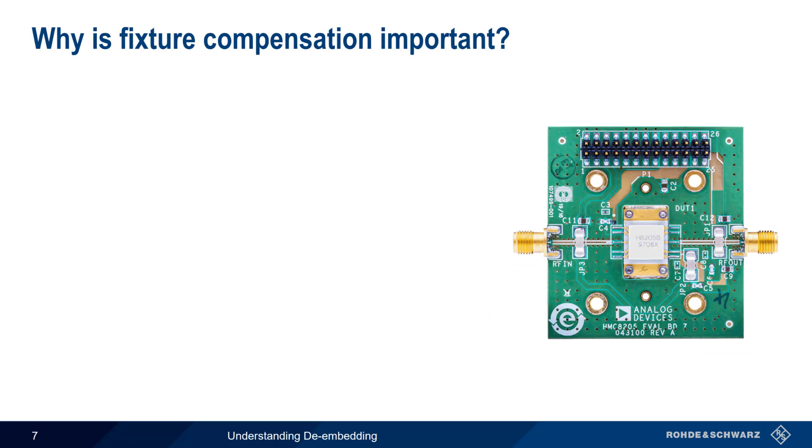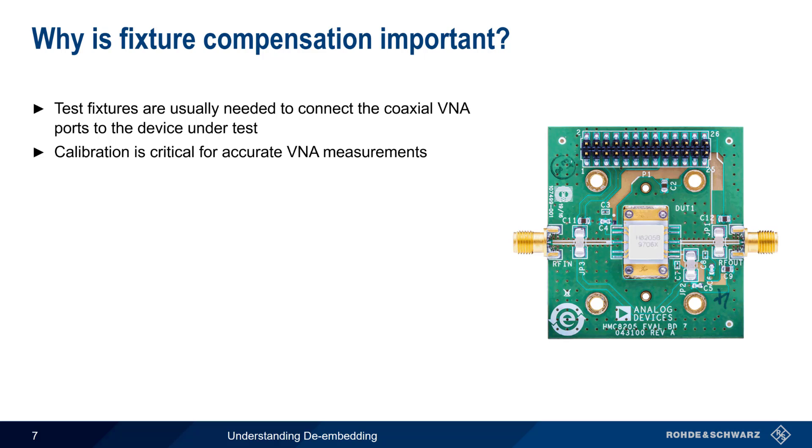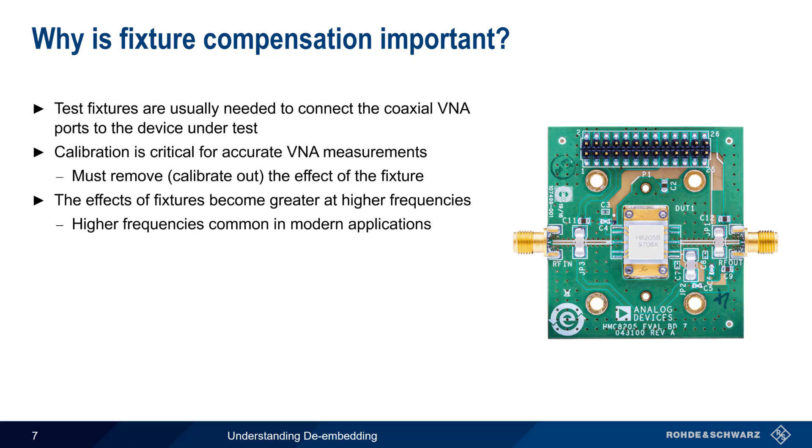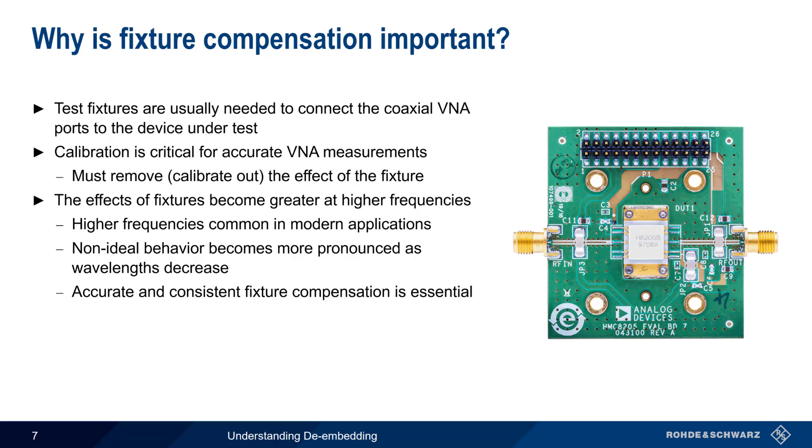So why is fixture compensation important? Clearly, we need some way of connecting the coaxial VNA ports to the device under test, even when the device under test is not connectorized. And as you should already know, calibration is critical for accurate VNA measurements. So it should be clear why we need a methodology or procedure that can compensate for, or calibrate out, the effects of the fixture. This need for fixture compensation is especially true at higher frequencies, and high frequencies are quite common in many modern applications. As frequency increases, wavelength decreases, and non-ideal behavior becomes more noticeable or more pronounced. For these reasons, accurate and consistent fixture compensation has become essential as applications move to these higher frequencies.